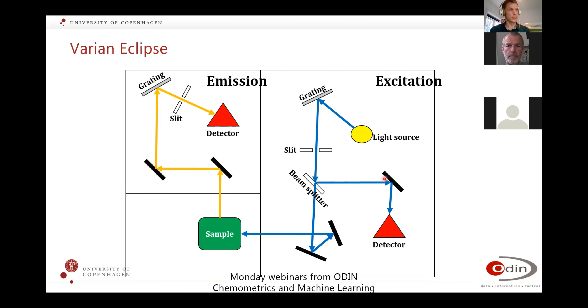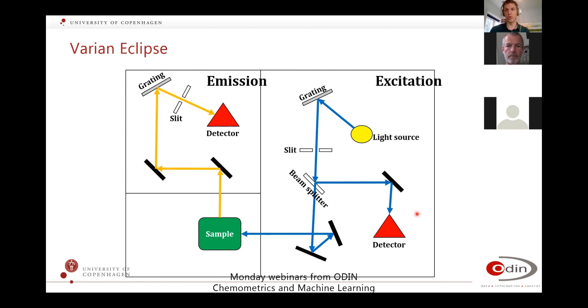In the beam splitter, some light travels to a reference detector. In some instruments this signal is used actively to correct the measured signal. In others it's more of an internal standardization that you as a user will never see, but it's recorded so the vendor can know if something is happening with the light source — if this detector signal starts going down, you know something is happening to the light source.